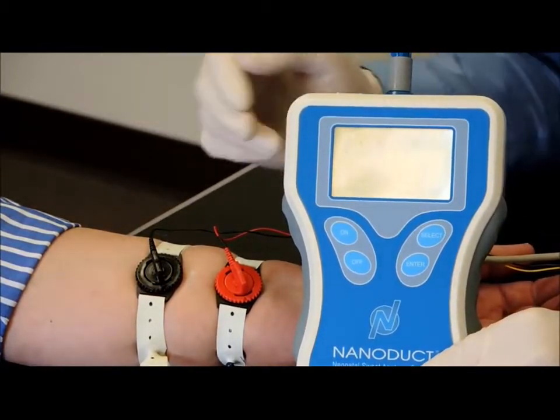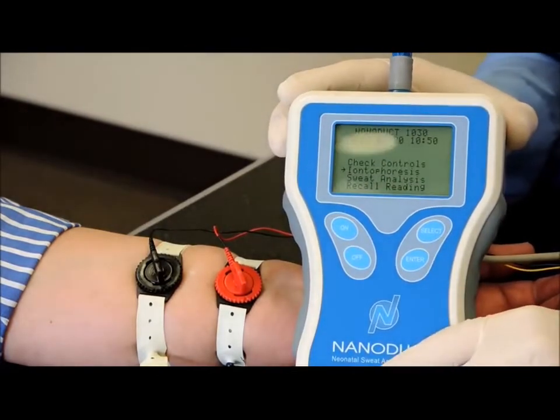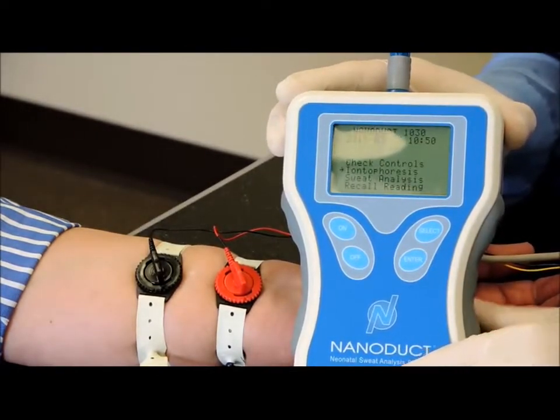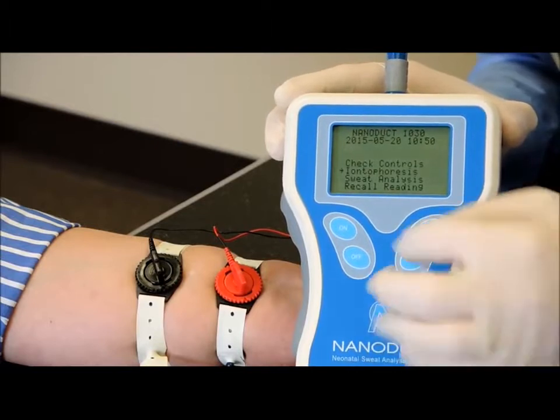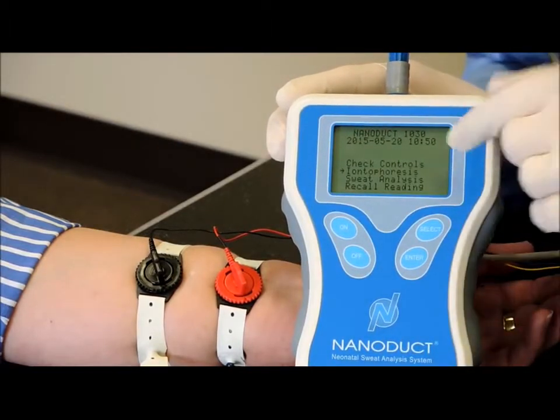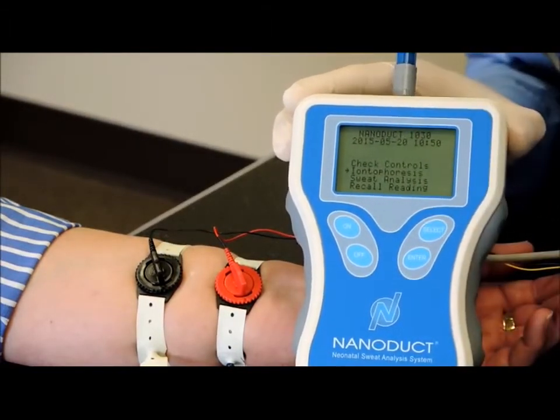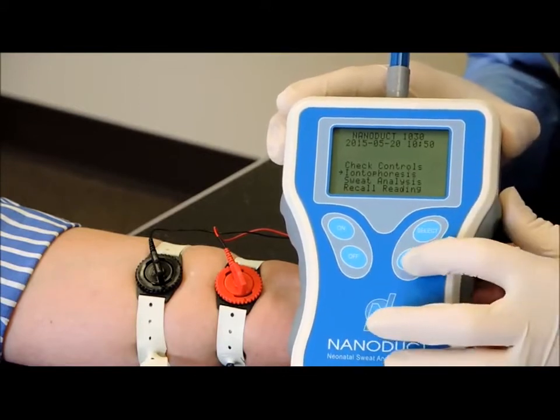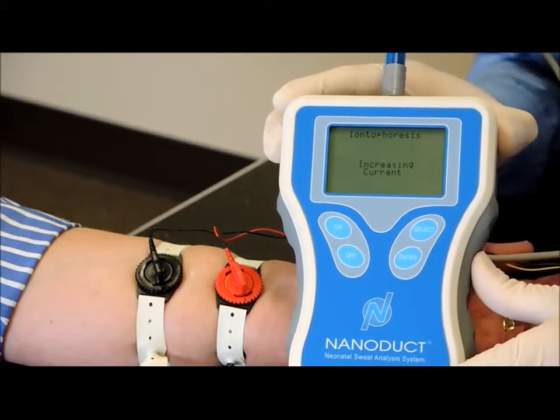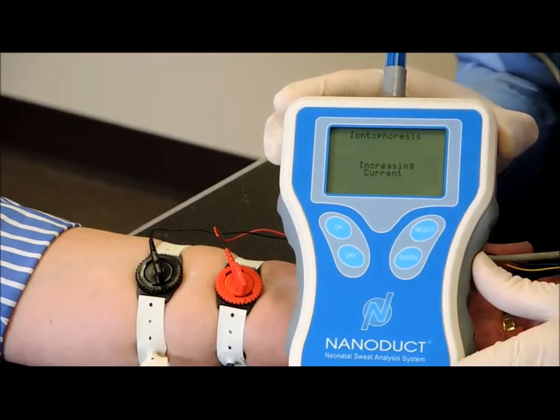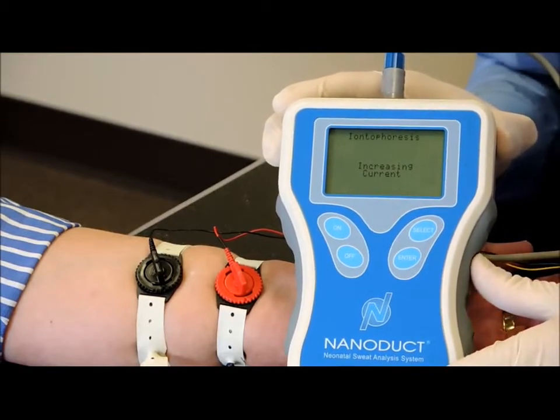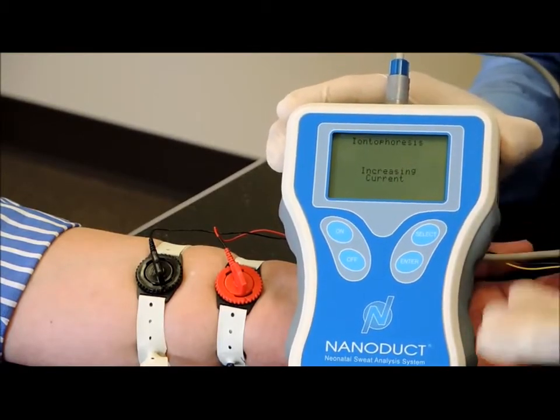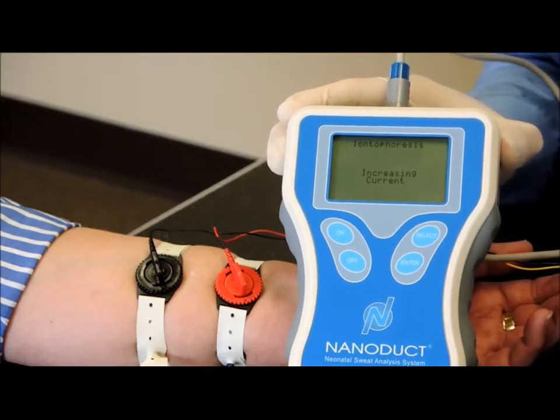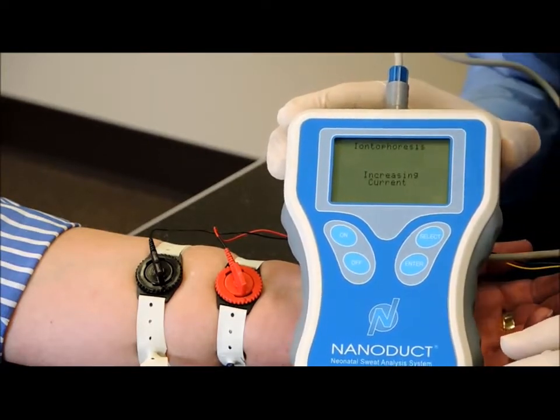Now with the electrodes in the holders and thus making contact with the skin and with the discs in place, always remember to have the discs there, we can now turn on the Nanoduct with the arrow pointed towards iontophoresis. I can press enter, and it will begin the iontophoresis process. This takes 2.5 minutes, and it ramps up the current and then holds the current steady, and then we'll ramp down the current.